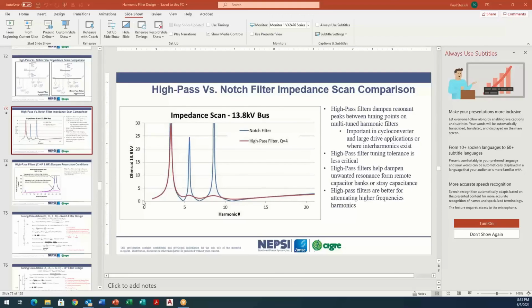Our recommendations, generally speaking: once you get a harmonic filter design, we do recommend that testing gets done at the factory. All harmonic filters are custom in nature, and therefore they should be treated as if you're going to type test the equipment. So we recommend in-post testing, high pot testing, and SFRA testing, which is frequency response analysis, to come up with an impedance profile similar to this, to confirm that your filter impedance profile matches that of the study, and then partial discharge testing to confirm that the system is going to last 20 years.